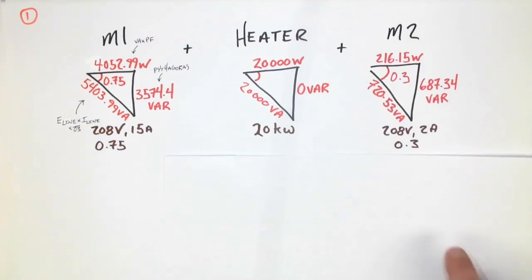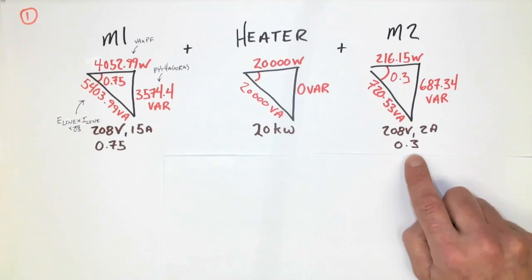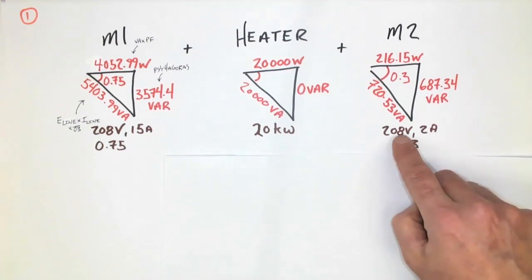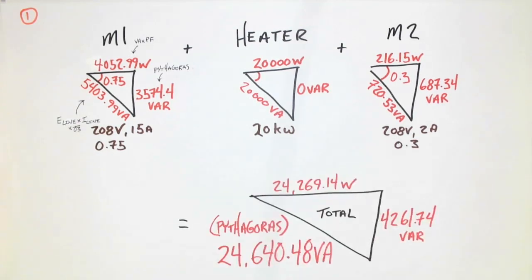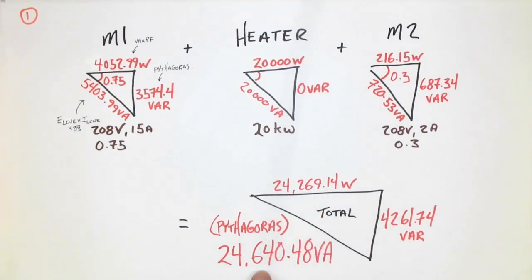The next item is motor two — 208 volt, 2 amp, 0.3 power factor. I multiply the two values times root three to get my VA, then use the power factor to get my watts and Pythagoras to get my VARs. Once I do all of that, I add all the verticals and all the horizontal components. Since we have all inductive loads, the VARs will all add together, giving us a total of about 24,000 watts and 4,261 VARs. Using Pythagoras with these two values, I get 24,640 VA.